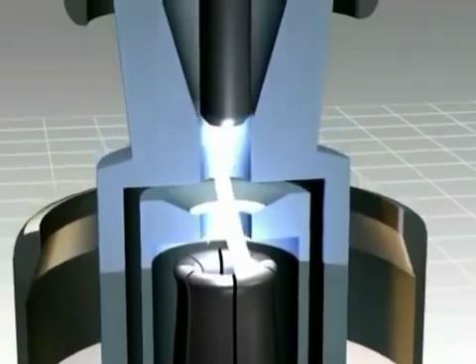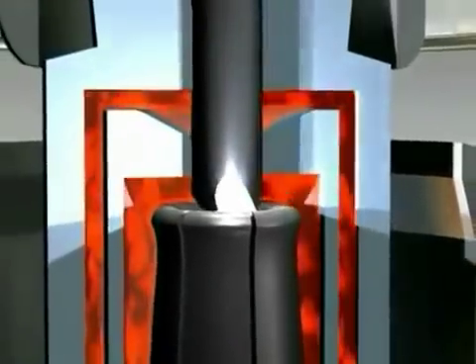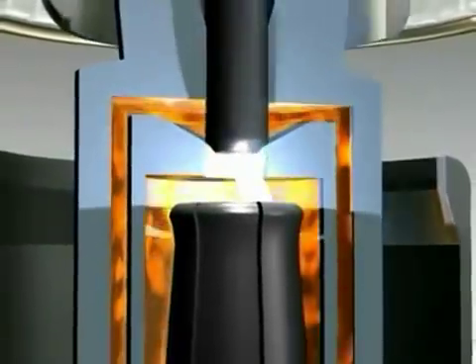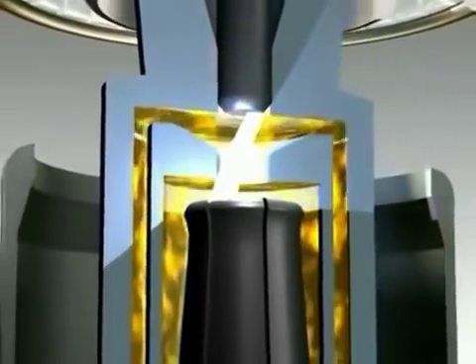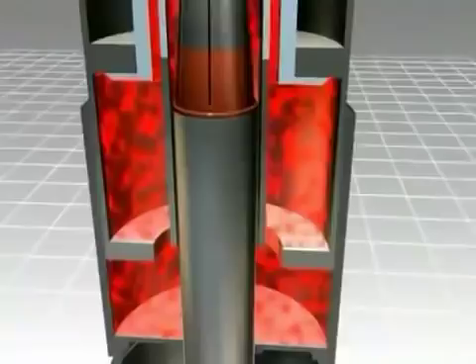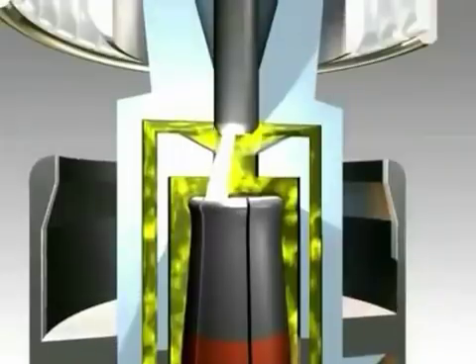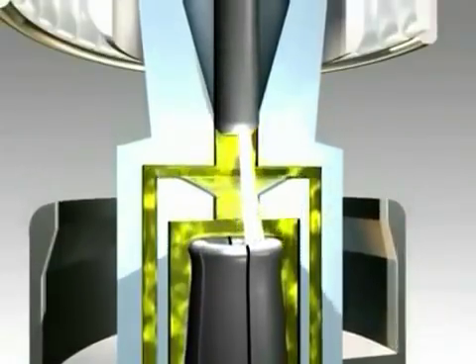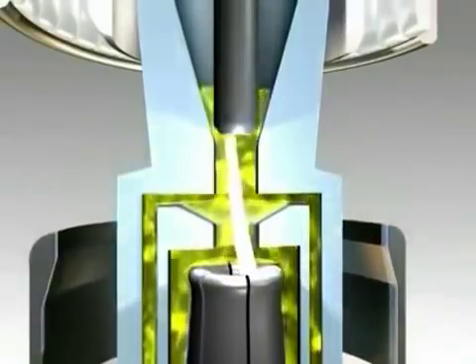At the same time, the contact cylinder moves into the base and compresses the arc quencher using sulfur hexafluoride. This gas compression generates a gas flow through the contact cylinder and the nozzle to the arcing contact. This way, the arc is extinguished.